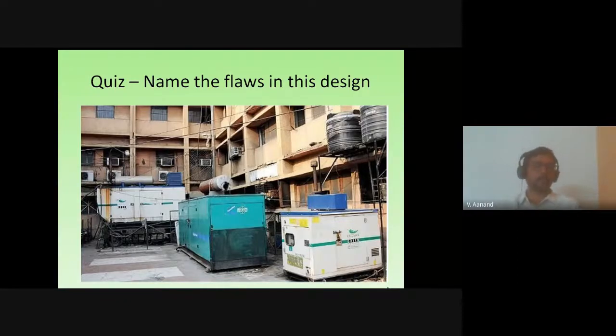You've actually covered most of the points. See, if you look at it, the water tank is placed right above the generator. Even if a raindrop falls on the enclosure, yes, the enclosure is designed to handle raindrops. But what if the water tank itself falls on the generator? If the structure weakens and it falls, the entire splash of some 1,000 liters will get into the generator, and this is a danger. It is not designed for such a huge splash.